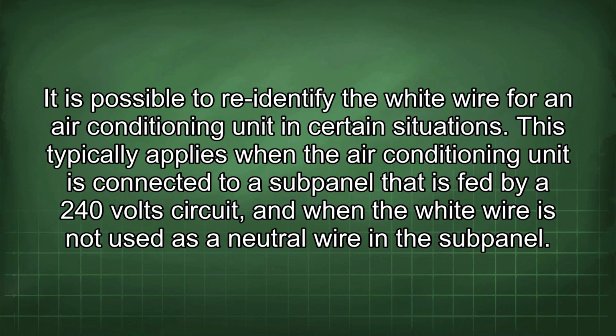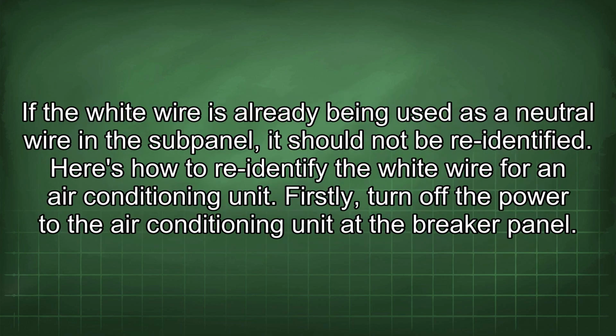It is possible to re-identify the white wire for an air conditioning unit in certain situations. This typically applies when the air conditioning unit is connected to a subpanel that is fed by a 240-volt circuit and when the white wire is not used as a neutral wire in the subpanel. If the white wire is already being used as a neutral wire in the subpanel, it should not be re-identified. Here's how to re-identify the white wire for an air conditioning unit.